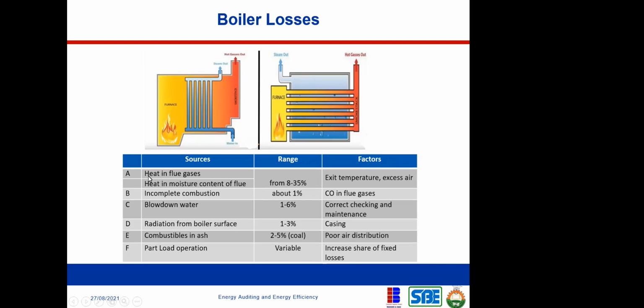I will explain this. So for the first one, you have heat in flue gases. Now, what is the flue gas? I talked earlier about these gases that are exiting from this point. After you've done the heating, some of the heat has been transferred to form the steam. Then the gas from the combustion will now escape. So when the gas from the combustion is leaving, it still contains a good sum of heat. So how do you capture that heat? You can actually save up to between 8 to 35% if you can capture the heat from that exit gas. Okay, so the factor here is exit temperature.